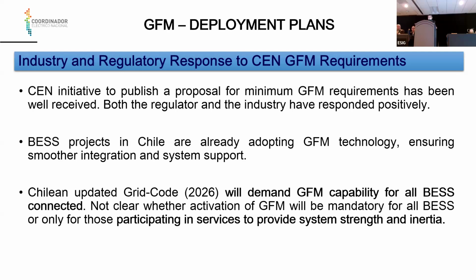Well, the BESS projects in Chile are already adopting grid forming technology because they know that the grid code will change next year. As I said, the Chilean regulator is updating the grid code, and one of the principal issues here is that they will demand grid forming capability for all BESS connected, new and existing. It's not clear whether the activation of the grid forming control mode will be mandatory for all BESS, or only those participating in services to provide system strength and inertia.